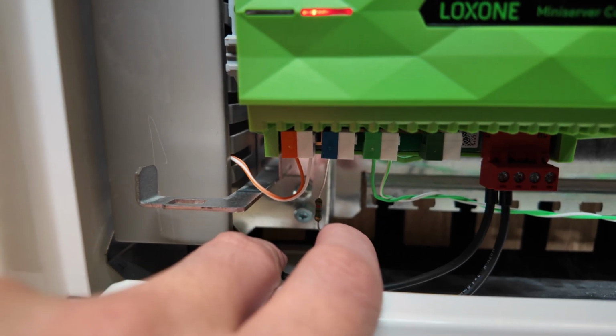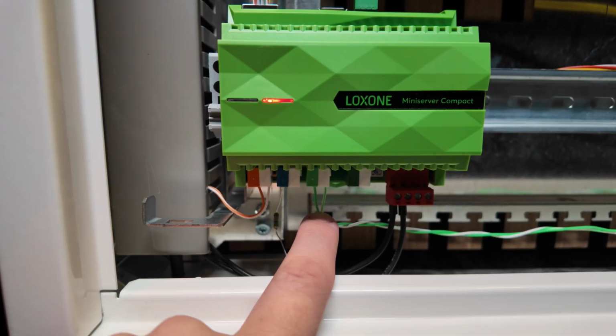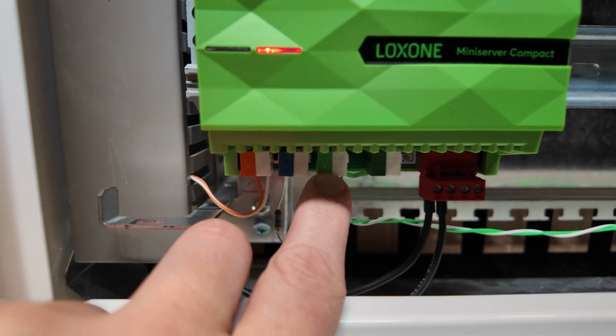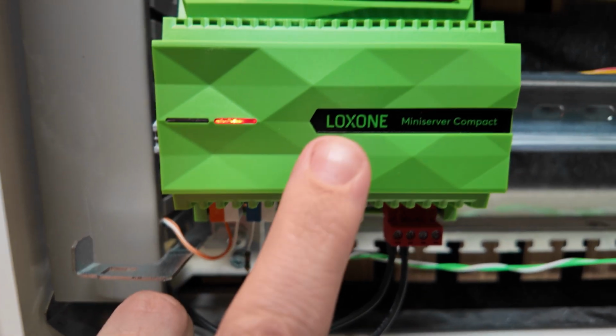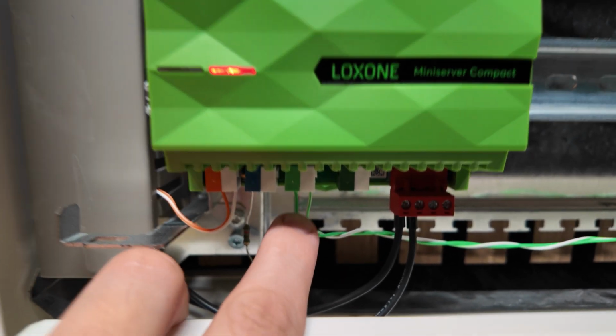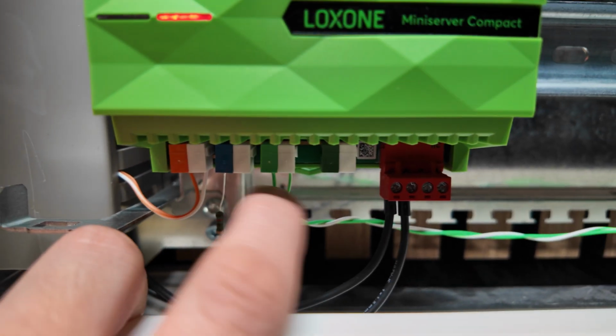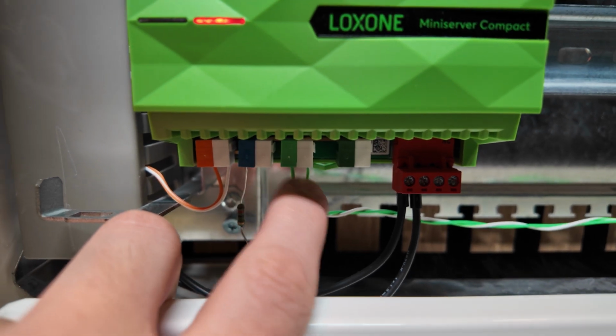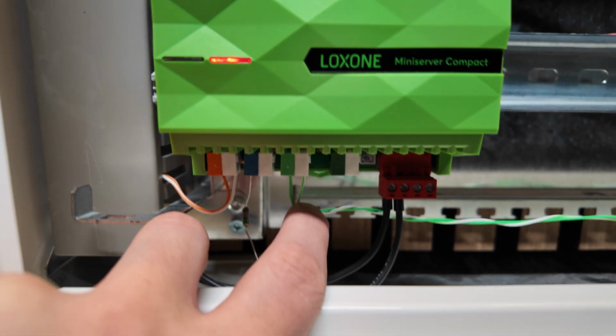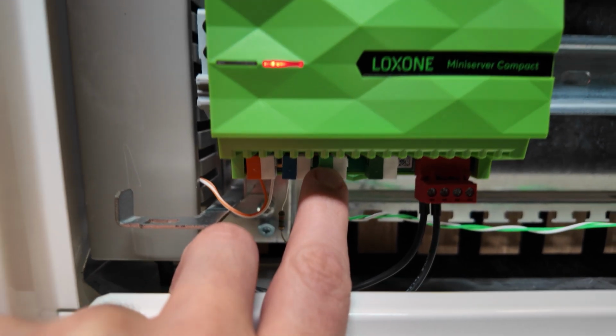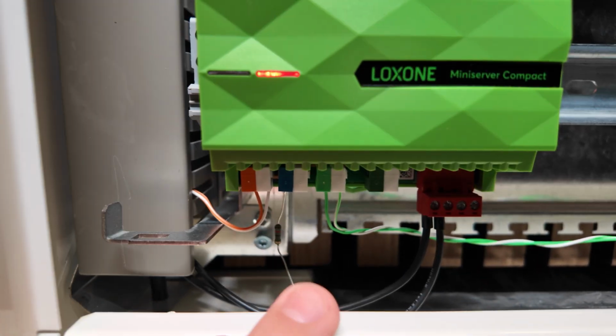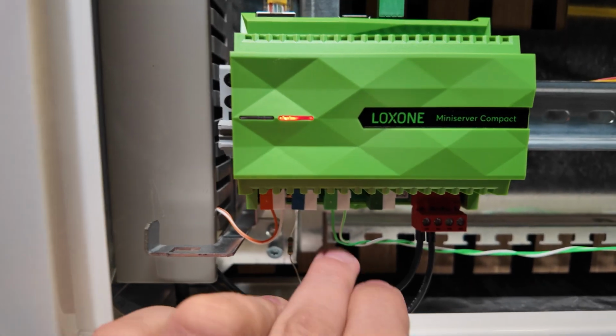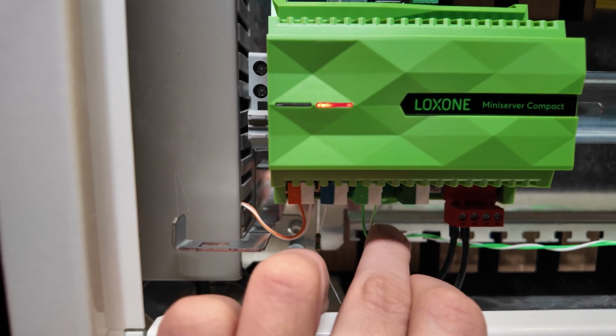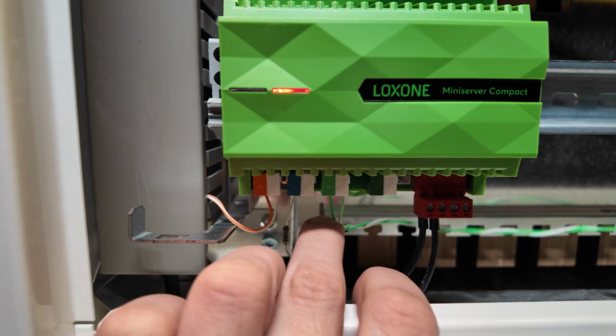I'm not 100% sure, but I think it's CAN bus here, the link. Then we have the Loxone tree bus. There is a tree extension with two of these branches on it. The mini server compact and normal mini server have one tree branch, so you can connect up to 50 devices per each branch. I typically plan for 30 and then I take another tree extension, because you never know what other devices Loxone brings to the market, so I'd like to have some spare ones on each tree line.